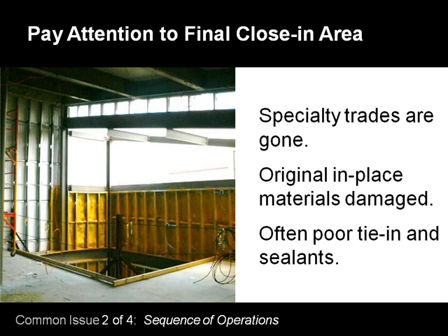So address these areas in terms of the overall building enclosure. As Jenn was noting before, we're talking holes, quarter of an inch, half an inch, 3/16 of an inch. A hole is a hole, as far as waterproofing, air tightness, and vapor tightness are concerned. So close in these final areas properly. You don't want to have these relying on duct sealant, as we were joking about before.